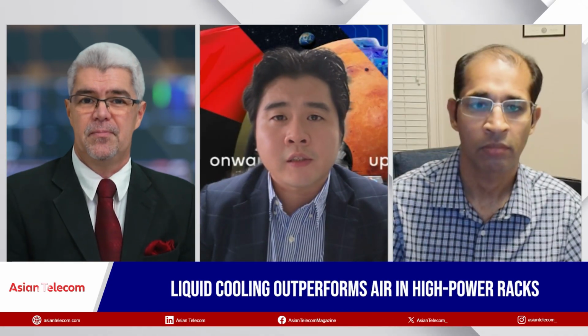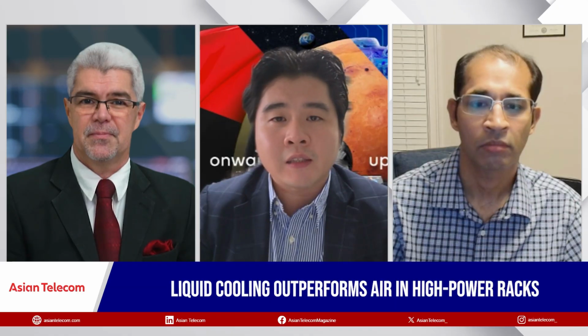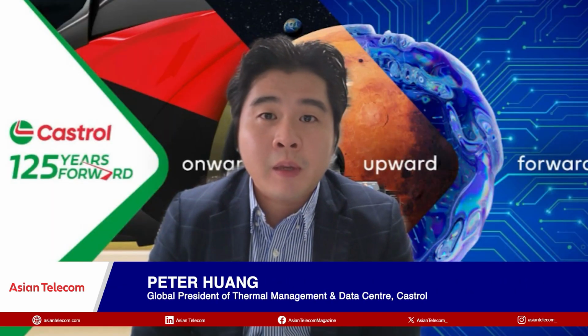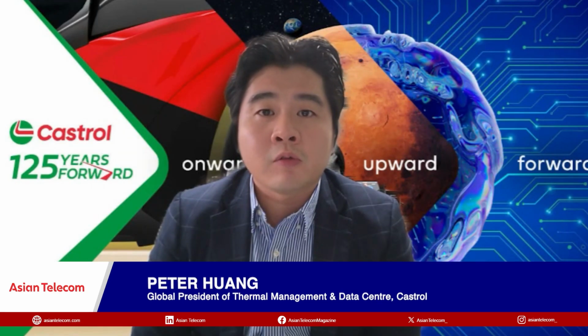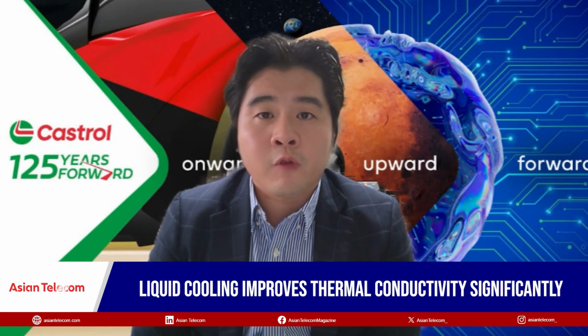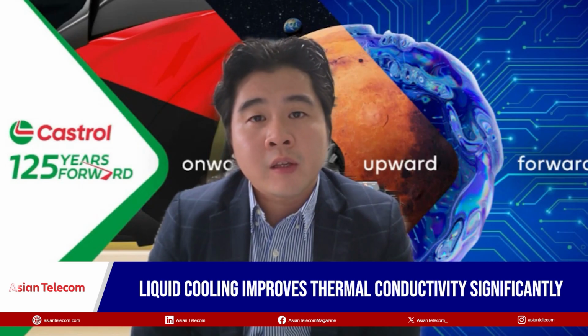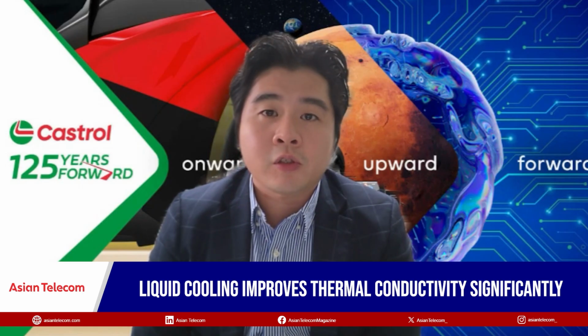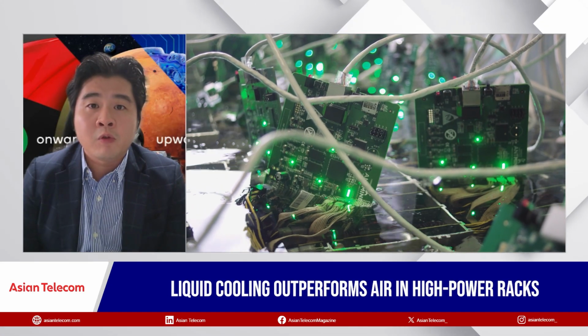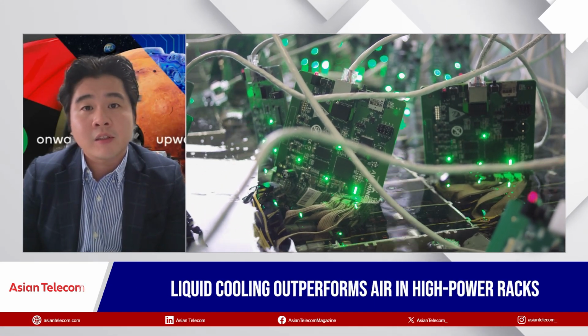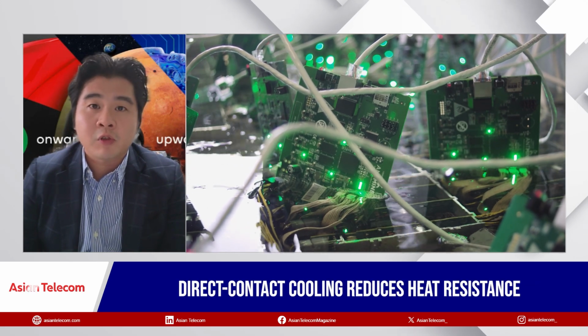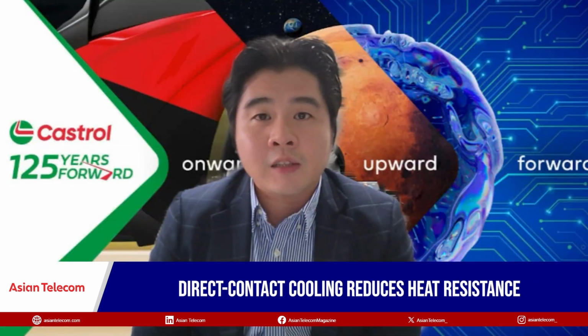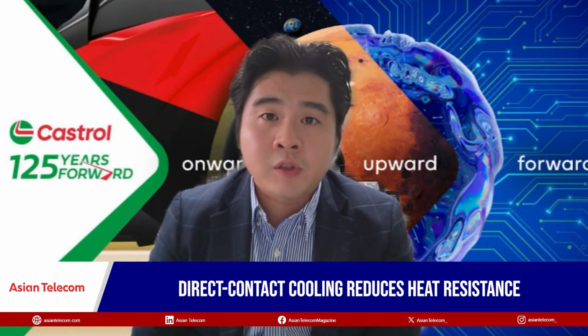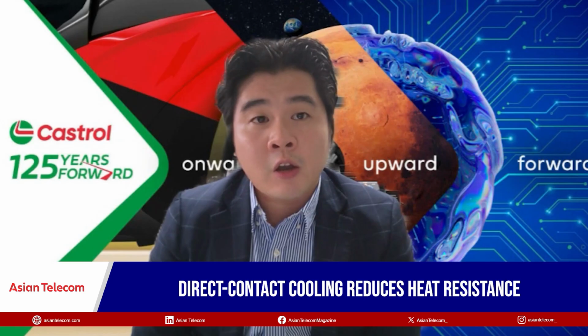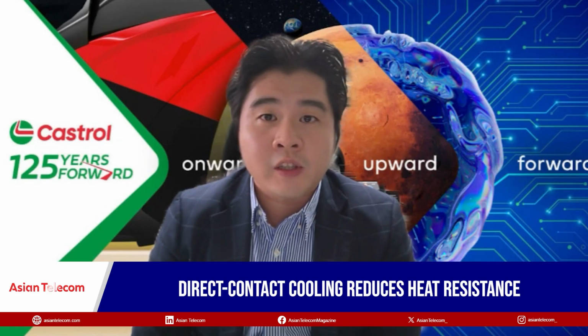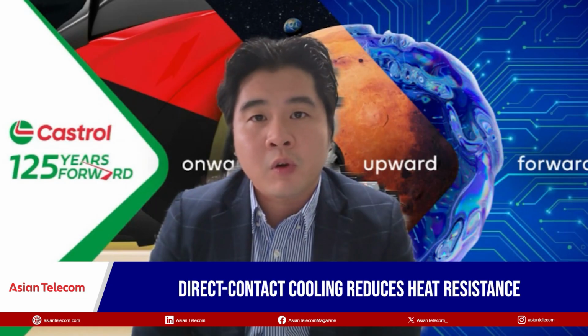Liquid cooling is essentially more effective because it has better thermal conductivity, meaning it's able to remove heat more than traditional air cooling. It's also more efficient, removing heat resistance because it's in direct contact with the heat source, the chip and the servers. Liquid cooling is proven to remove up to 80% of the energy used for cooling the data center, so it's proven to be more efficient.